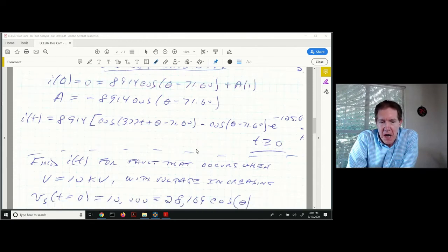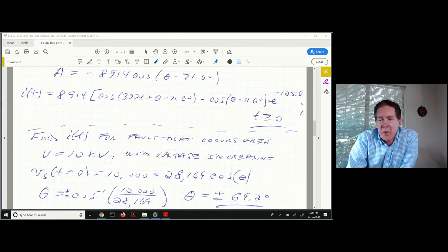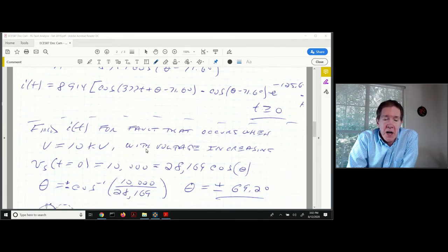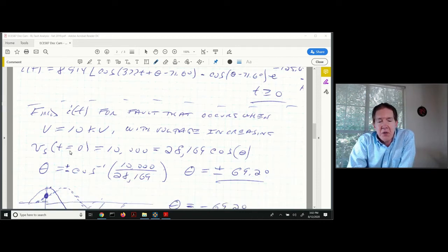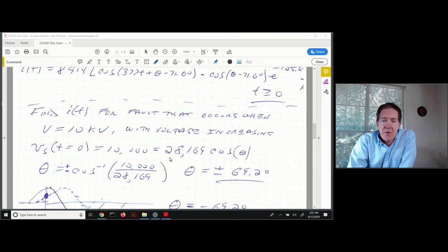How do I work in what theta is going to be? I've got another condition that says I want to figure out what this fault current is if the fault occurs when the source voltage is 10 kV with voltage increasing. This is a zero peak value when this voltage is actually increasing. At time equals zero, I take that source voltage and set that equal to 10,000. We had a peak value of 28,169. At time equals zero, I have cosine of theta, and I need to solve for theta.